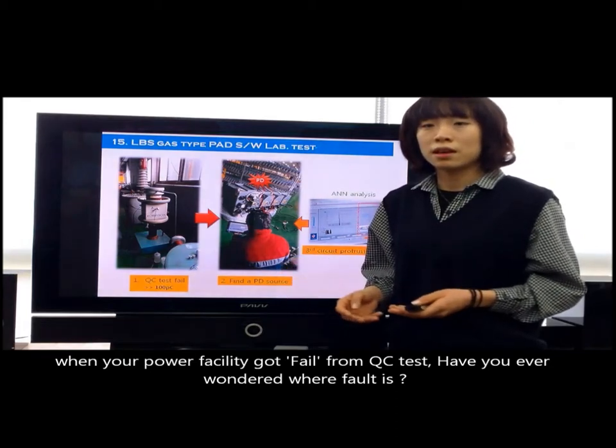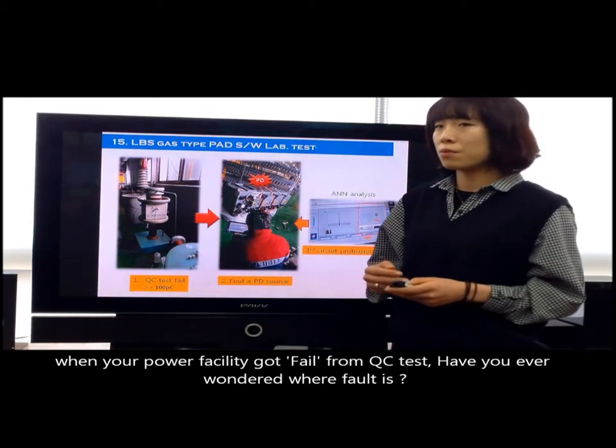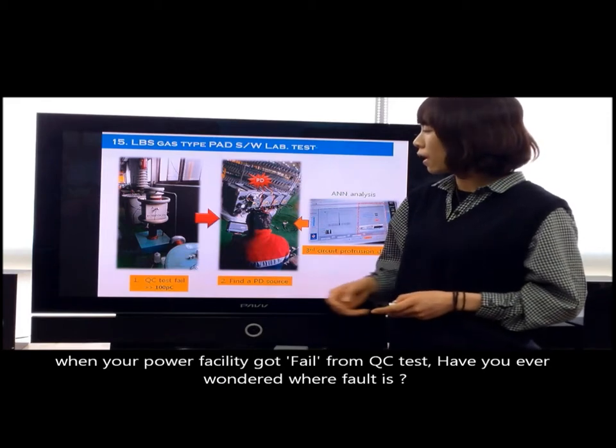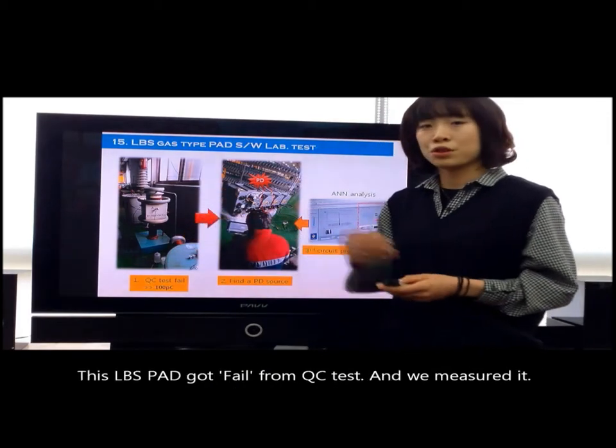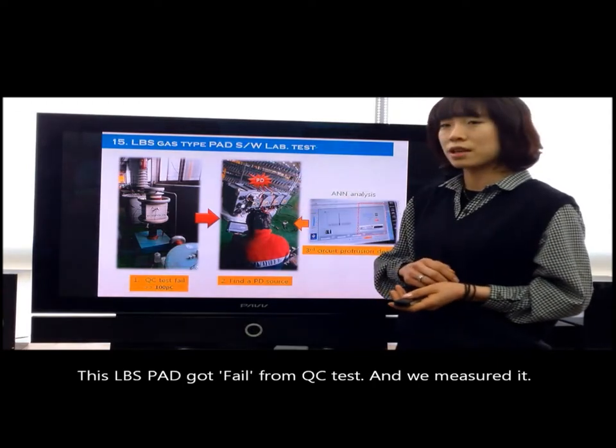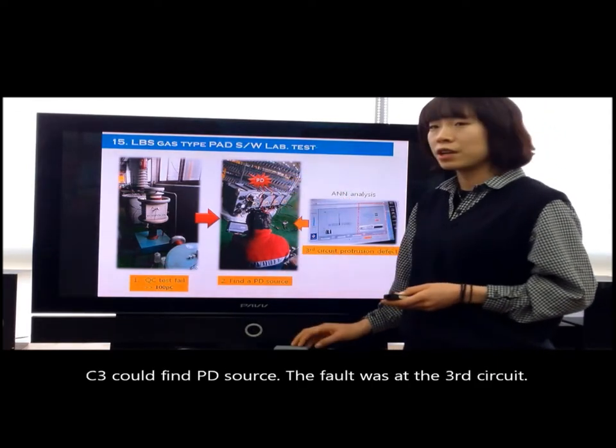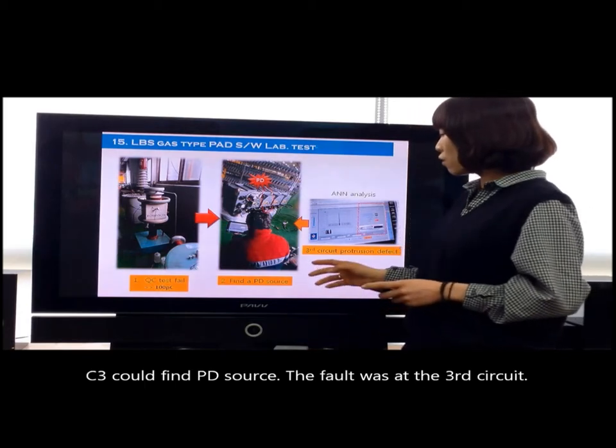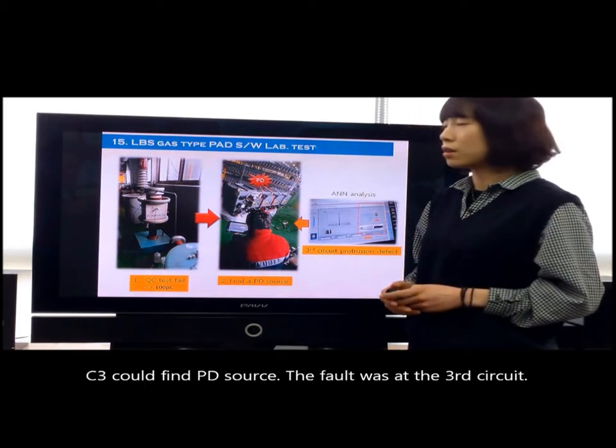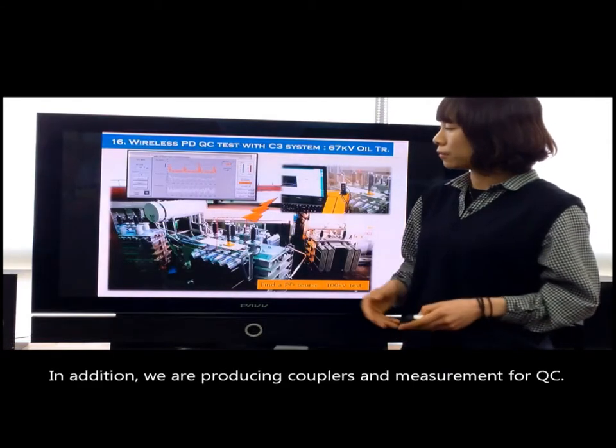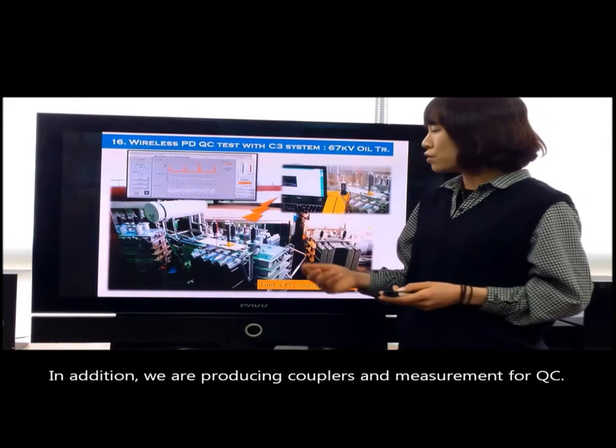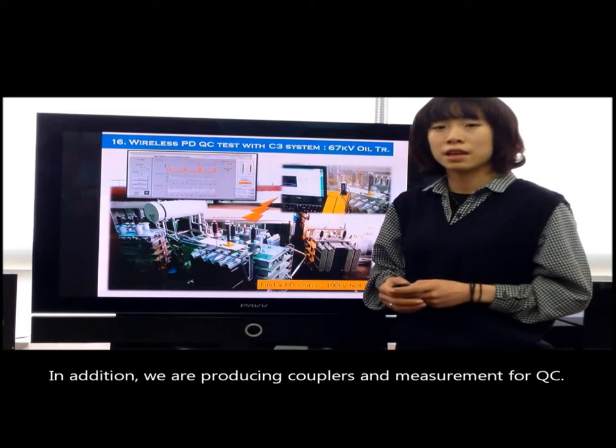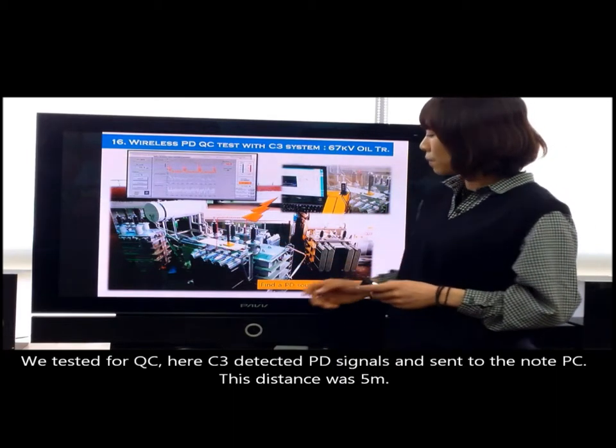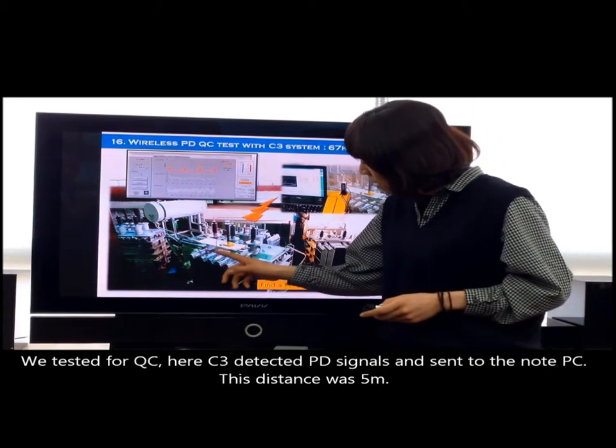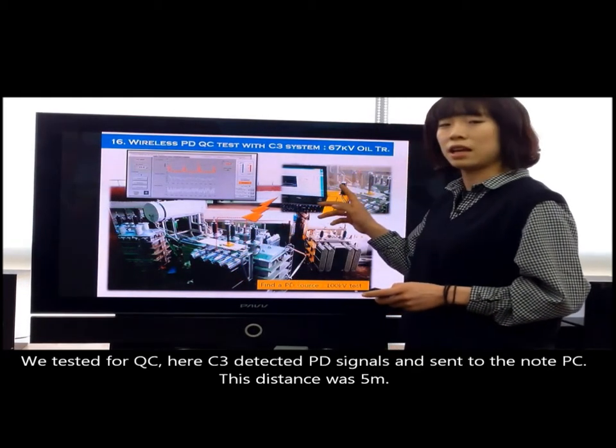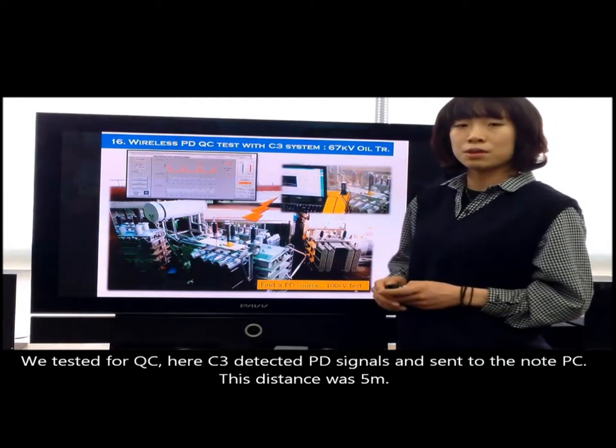When your power facility fails a QC test, have you ever wondered where the fault is? This LBS pad failed a QC test, and we measured it. C3 could find the PD source. The fault was at the 3rd circuit. In addition, we are producing couplers and measurement for QC. When we tested for QC, here C3 detected PD signals and sent them to the Note PC. This distance was 5 meters.